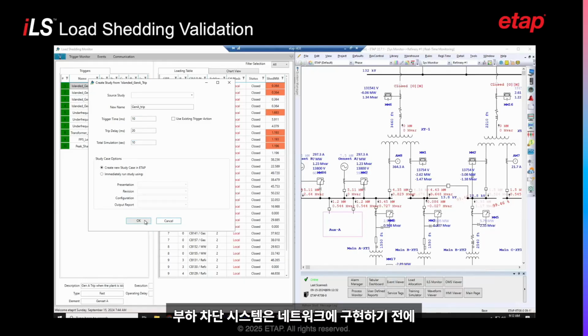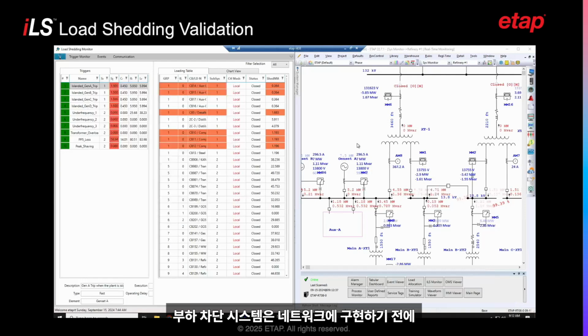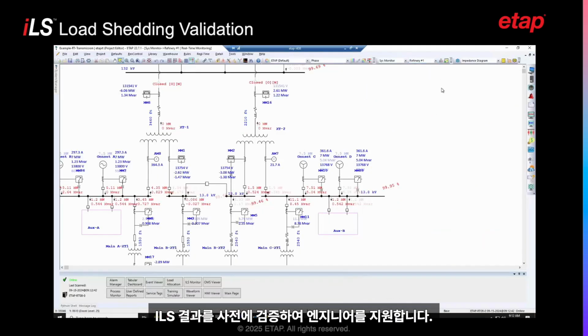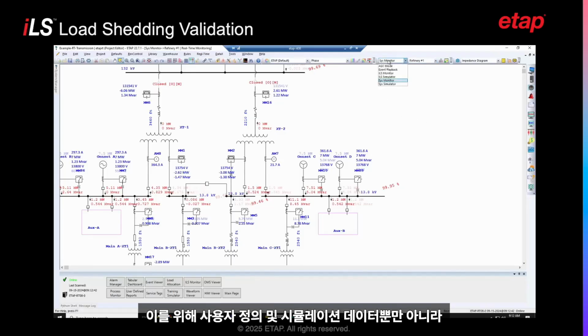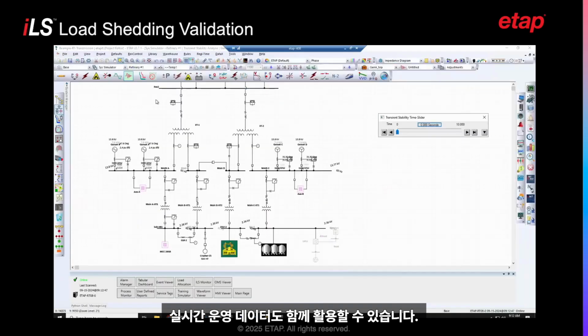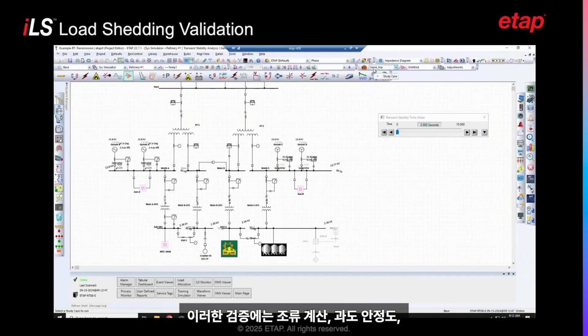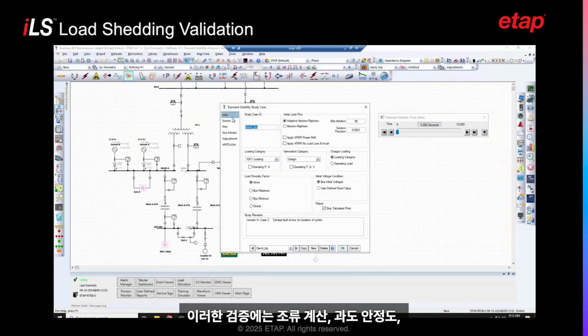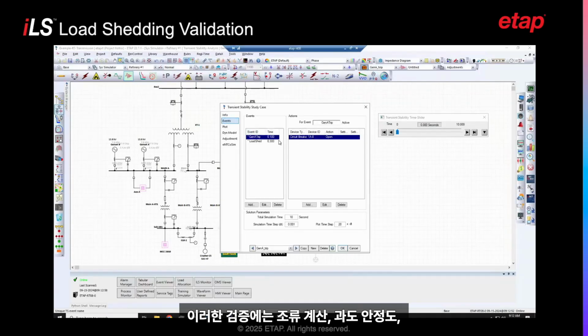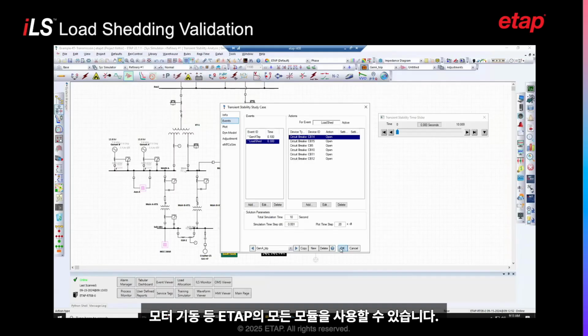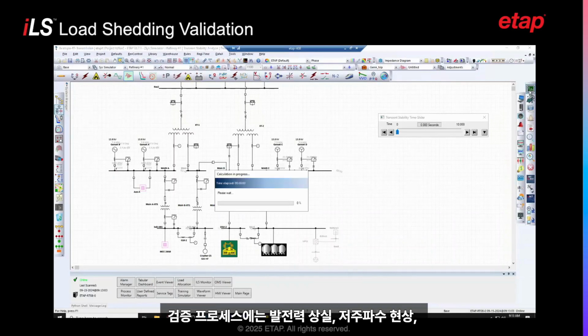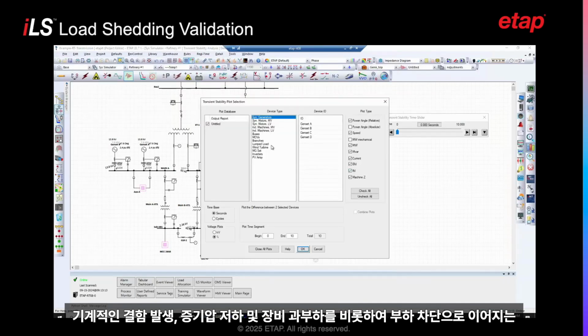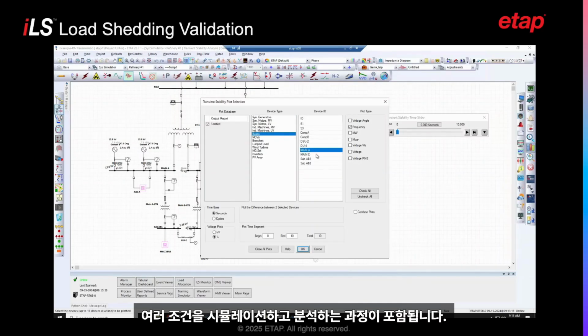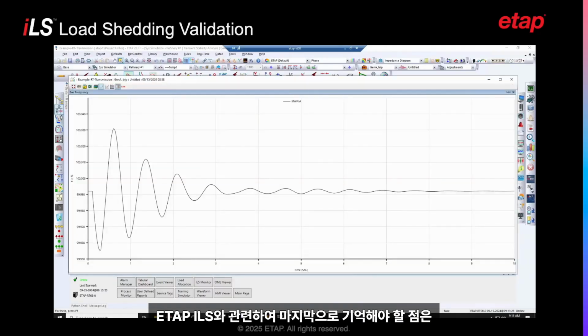The load shedding system supports the engineer by validating the results from ILS before implementing this within the network. It can utilize real-time data as well as user-defined and simulated data. All the modules within ETAP are available to perform such validations, such as load flow, transient stability, motor acceleration, and more. The validation process can consist of simulating and analyzing loss of generation, under frequency, mechanical failures, steam pressure decays, overloads, and other conditions leading to load shed.